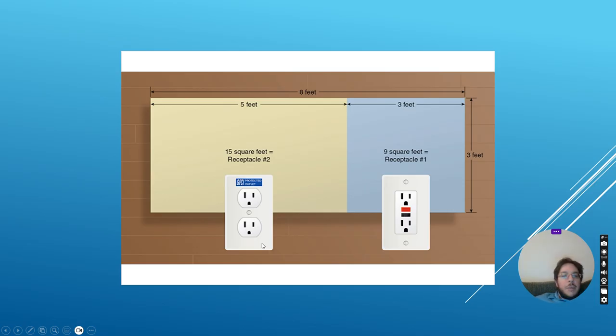So, keeping that in mind, it's the first 9 square feet of island or peninsula needs a receptacle, and then if you're more than 9 square feet, then you need another receptacle for every additional 18 square feet. So this is a bigger island, so then we have to have a second receptacle. So the first receptacle will be within the first 3 feet, and the next receptacle will be within the next 5 feet. And then if this thing was even longer, then you need a third receptacle.